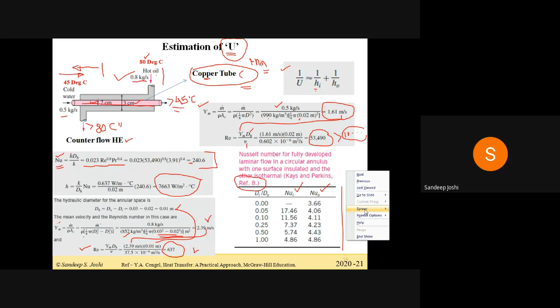Okay, so in this case, there are certain important points to understand. Let us observe the first solution here. For the internal flow, the flow rate was 0.5 kg per second, and this is the cold water flowing through 2 centimeter tubes, where at the inner surface Nusselt number is 240 and the heat transfer coefficient is 7,663. And the outer tube, where there is the oil with a flow rate of 0.8 kg per second, the Nusselt number is very less, that is 5.45, and the heat transfer coefficient is 75.